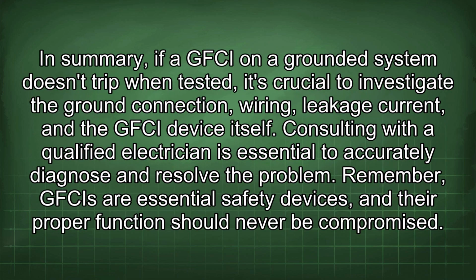In summary, if a GFCI on a grounded system doesn't trip when tested, it's crucial to investigate the ground connection, wiring, leakage current, and the GFCI device itself. Consulting with a qualified electrician is essential to accurately diagnose and resolve the problem. Remember, GFCIs are essential safety devices, and their proper function should never be compromised.